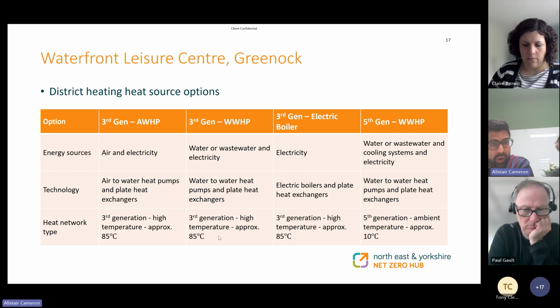So for us to make the system work at day one, we would have to operate the heat pumps at a high flow temperature. So the third generation, which we classify as high flow temperature heating, you'd essentially be running the heat pumps at an 85 degree flow to complement the existing heating network. So option 1, air source heat pump. Option 2, water to water heat pump, either using the River Clyde or wastewater from the sewage pipe. And then option 3, which is the low cost solution, which is essentially just using electric boilers and not taking advantage of any coefficient of performance.